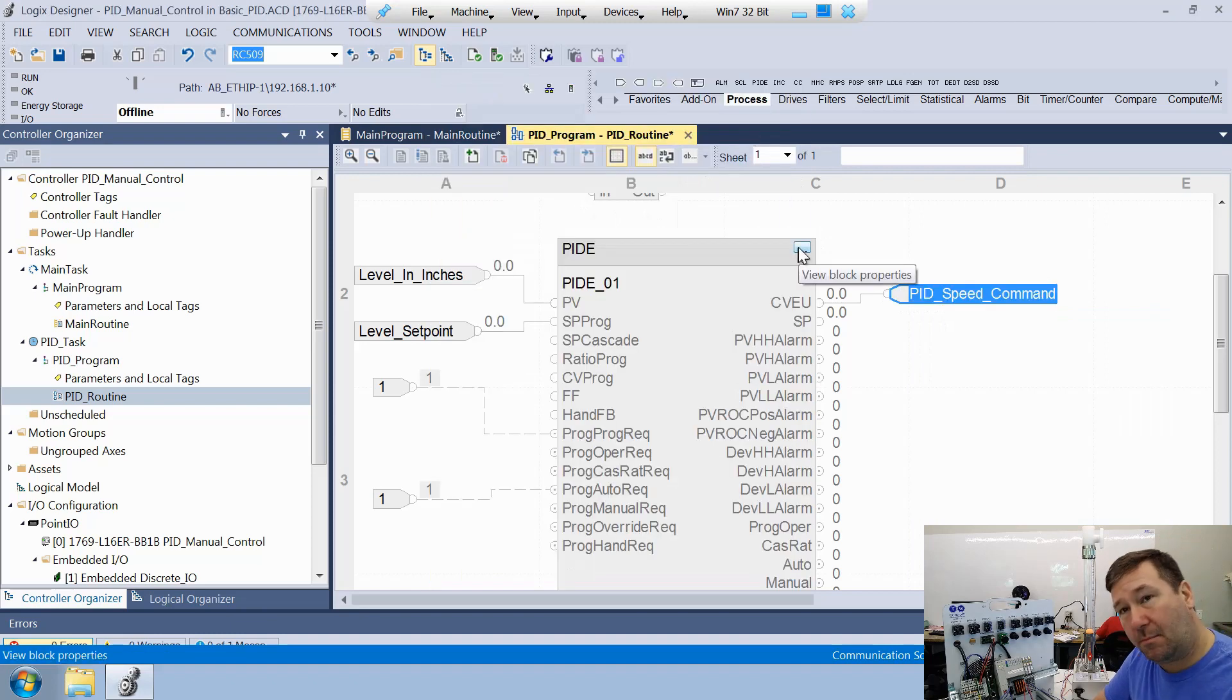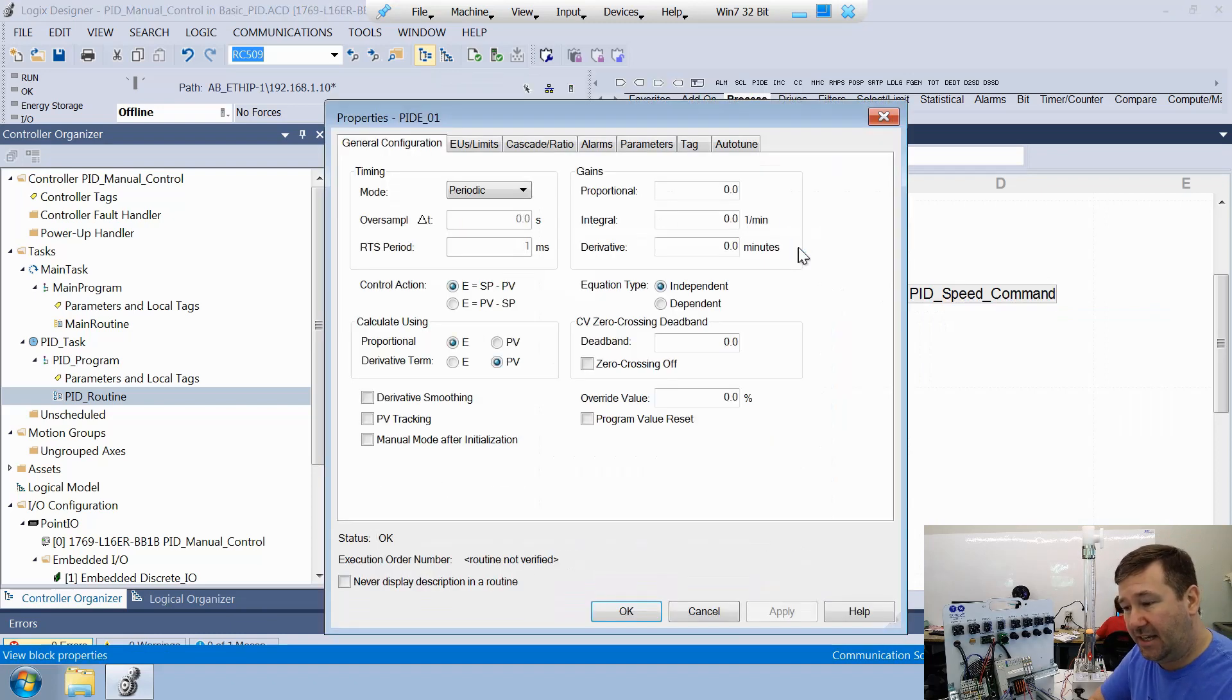And then we're going to view the block properties of our PID. And just for starting point, we do need to have something in this proportional and integral. So I'm just going to put a one in the proportional and I'm going to put a 0.1 in the integral. And then for our equation type, we're going to use the dependent variable equation. We'll actually have some videos later using the independent variable equation.